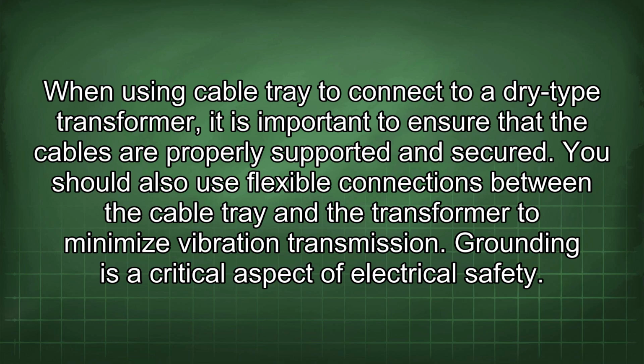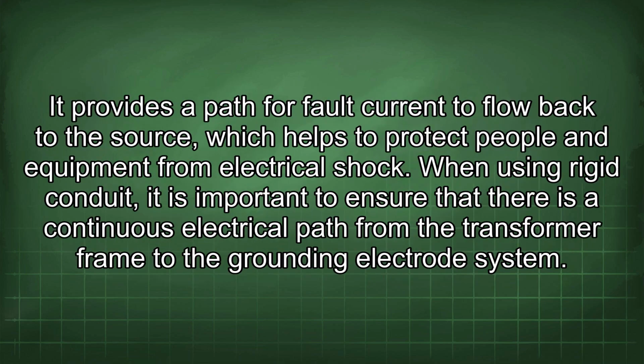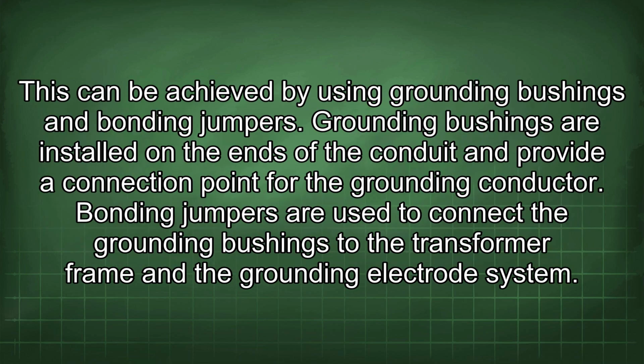Grounding is a critical aspect of electrical safety. It provides a path for fault current to flow back to the source, which helps to protect people and equipment from electrical shock. When using rigid conduit, it is important to ensure that there is a continuous electrical path from the transformer frame to the grounding electrode system. This can be achieved by using grounding bushings and bonding jumpers. Grounding bushings are installed on the ends of the conduit and provide a connection point for the grounding conductor. Bonding jumpers are used to connect the grounding bushings to the transformer frame and the grounding electrode system.